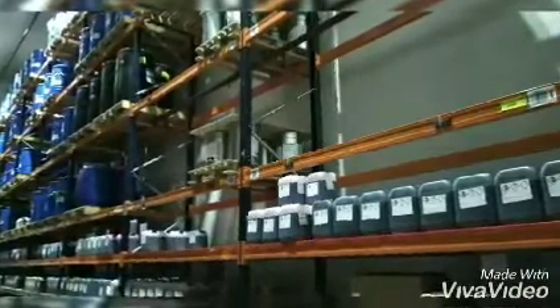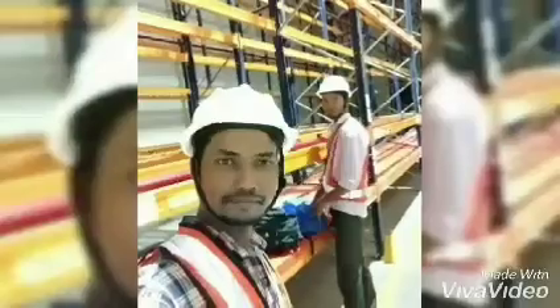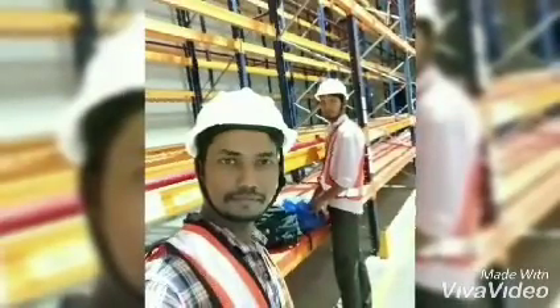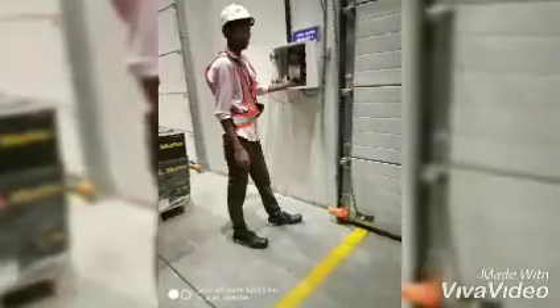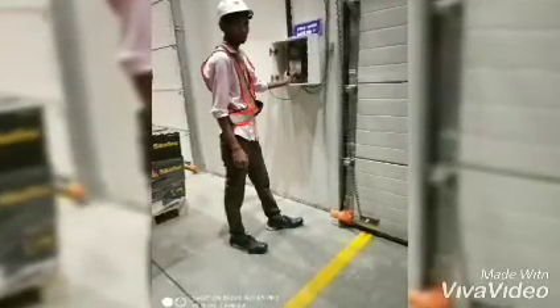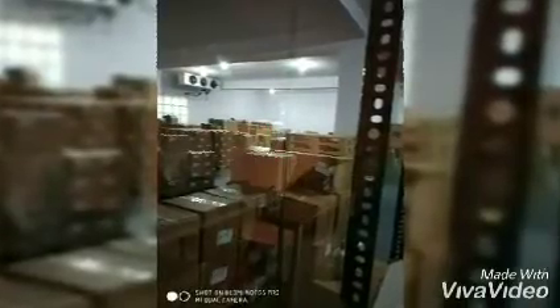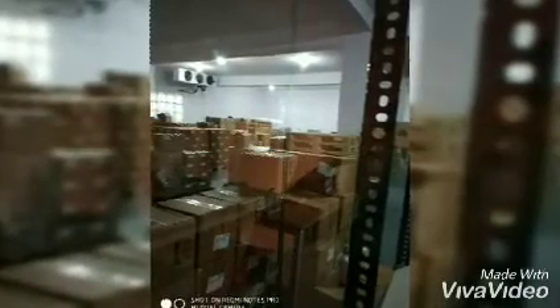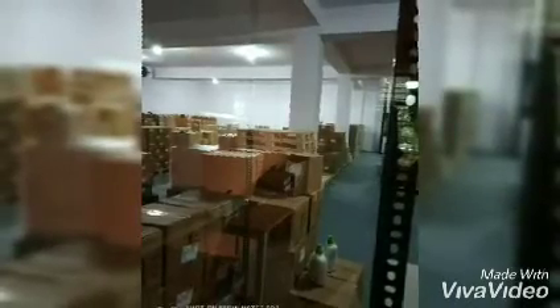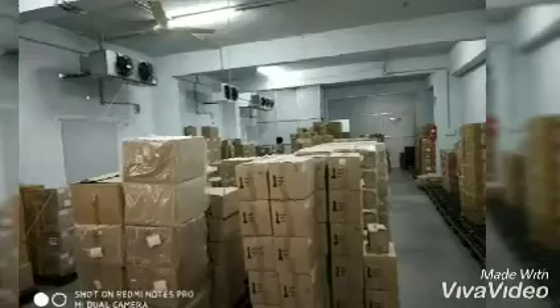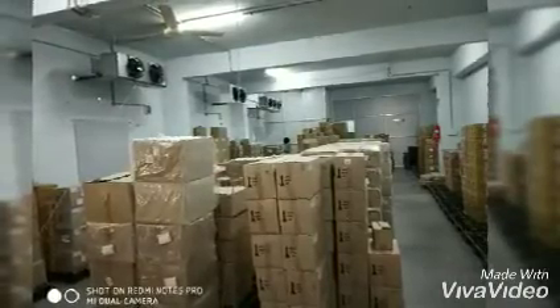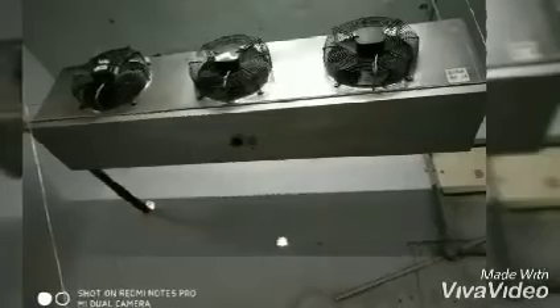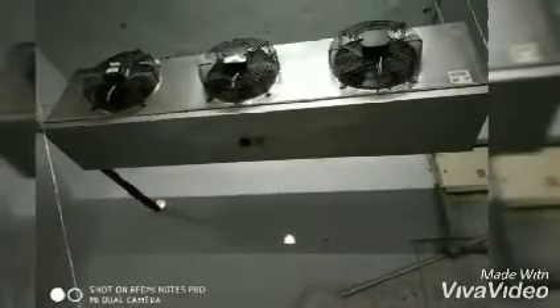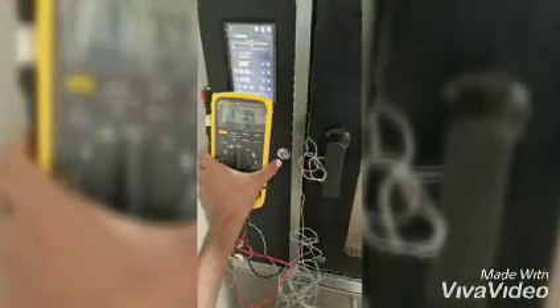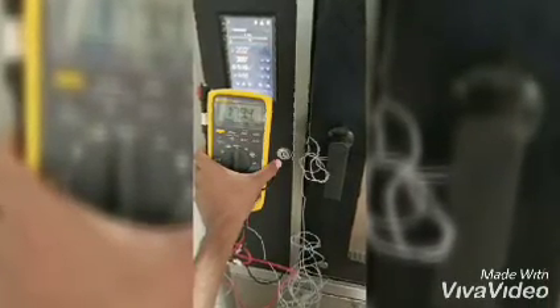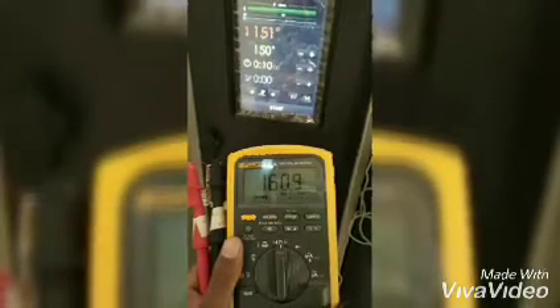This study must verify that all product will be subject to the same thermal environmental conditions, no matter where the product is situated within the processing compartment. This verification is mandatory and applies to all environmental process and storage equipment such as freezers, refrigerators, cold rooms, cool rooms, warehouses, delivery vans or reefer vehicles, transport containers, stability chambers, freeze dryers and incubators. Heat distribution studies of large storages and warehouses require sensors to be fitted strategically throughout the storage shelving, covering a percentage of the shelving area horizontally and vertically.